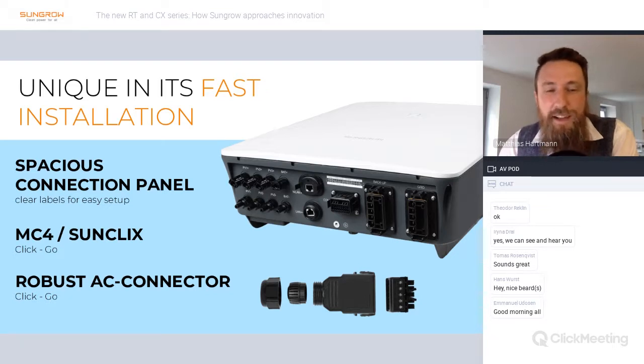They're really meant to last. On the left-hand side, there's the DC connection panel. For the PV, we use MC4 connectors. For the battery, we use a SunClix connector. So it's physically incompatible. In case you disconnect the inverter and want to reconnect it later, there's no way to falsely connect the battery to the PV inlet. So it's really a neat feature.